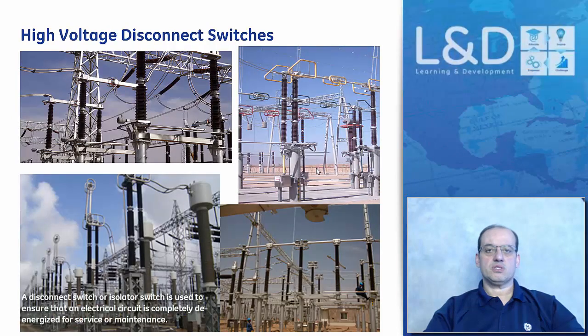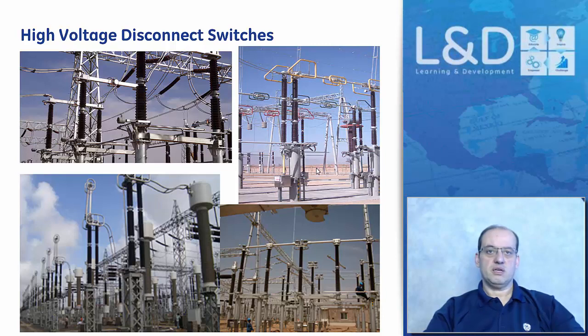A couple of examples of a high voltage disconnect switch. Basically flexible design configuration from 126 to 800 kV, including both horizontal and vertical configuration, center, side, double-sided, and V-breaker designs, designed for minimum but reliable clearance between phases and vertical length. Conductive parts are constructed of lightweight, strong aluminum alloy, and driving parts and balanced spring are enclosed to minimize environment exposure. They've got a hot dip galvanized process on all exposed iron and steel parts, which provides an excellent anti-corrosion capability. Height of porcelain and perpendicular may be adjusted via regulating bolts to ease insulation. Earthing switches are available at both ends of the frame.